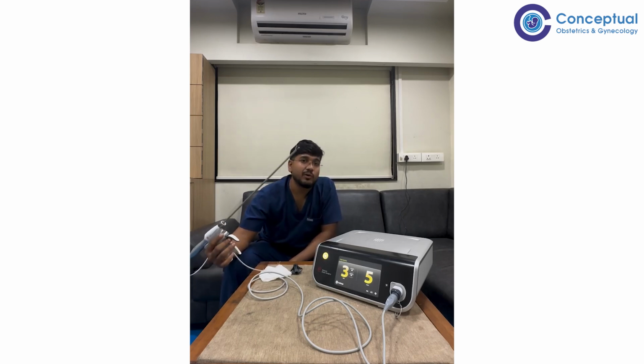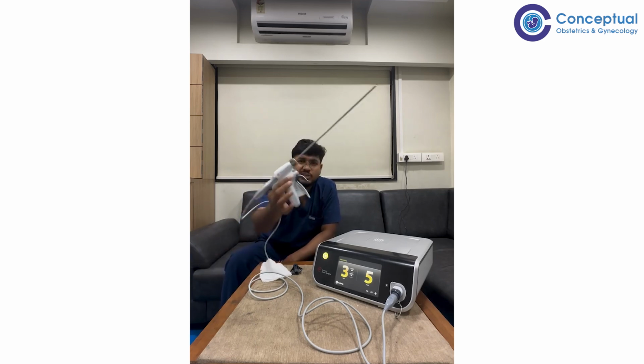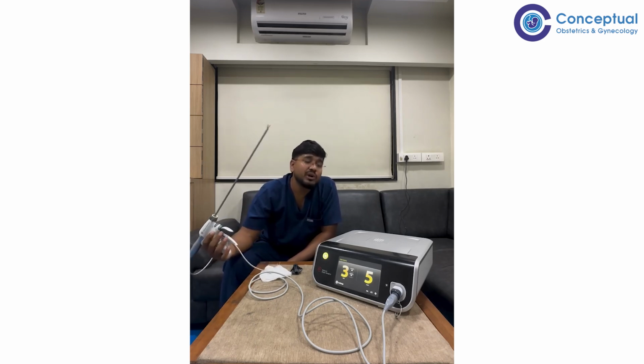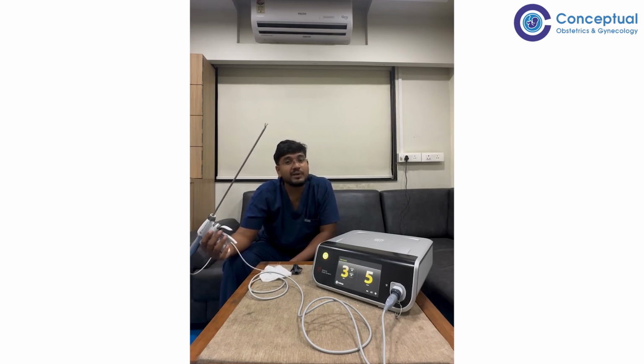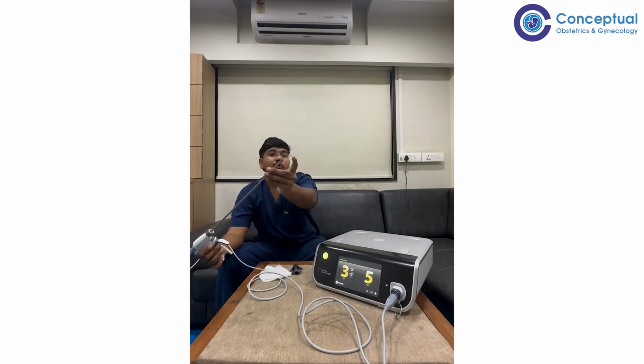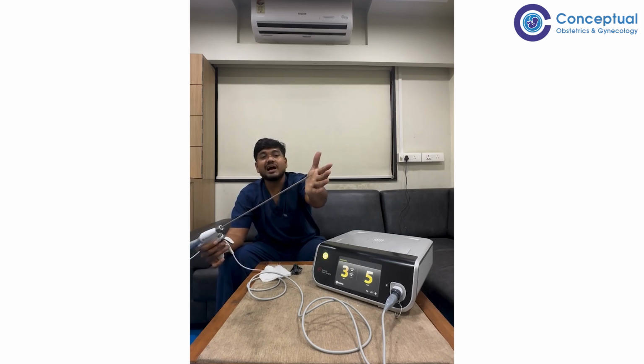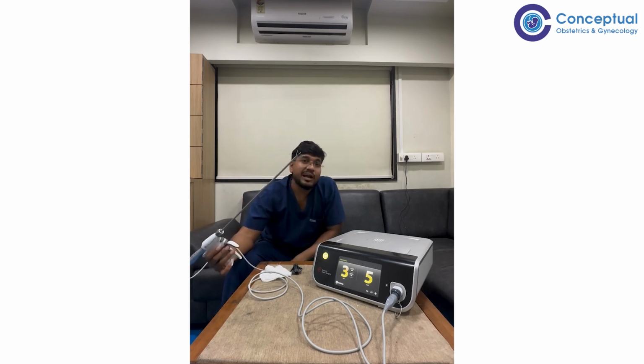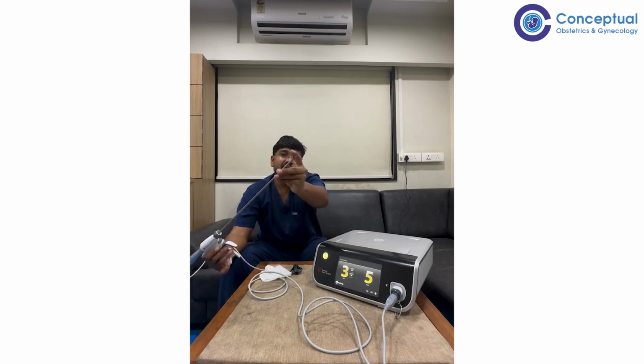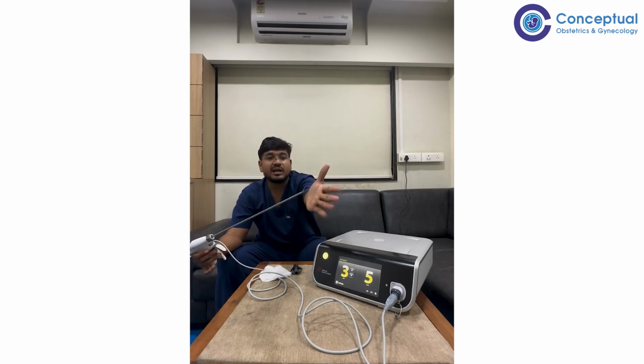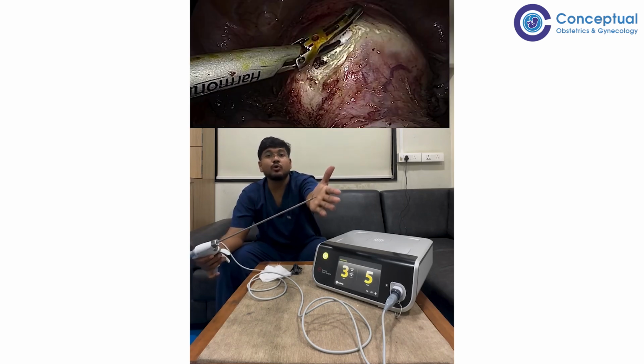Second application that I want to bring your notice to is called as backscoring. This instrument is also called a harmonic scalpel. Have you ever thought why? Because standalone, only using this active electrode and not using the jaw, you can use it like a scalpel inside the abdomen. And how is that? You don't need the non-active jaw. You only need the active probe which is moving, and you start using it like a scalpel over the tissue.